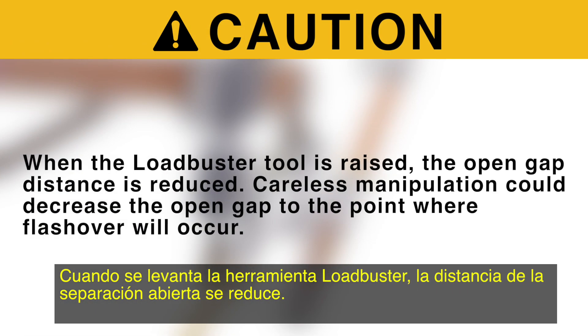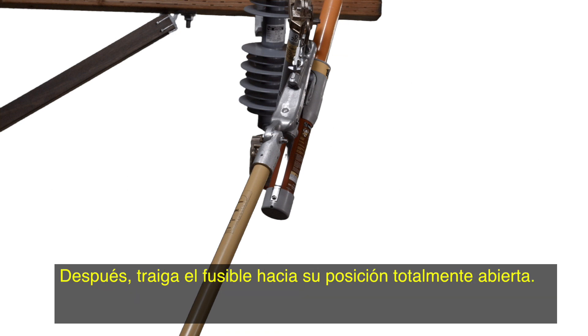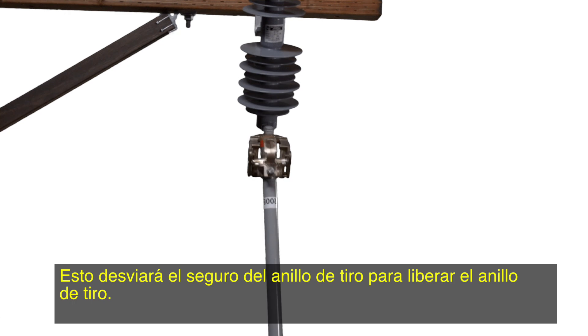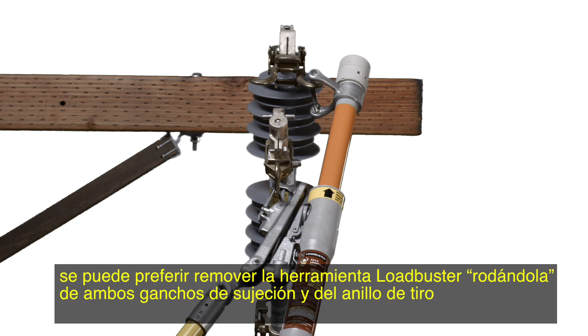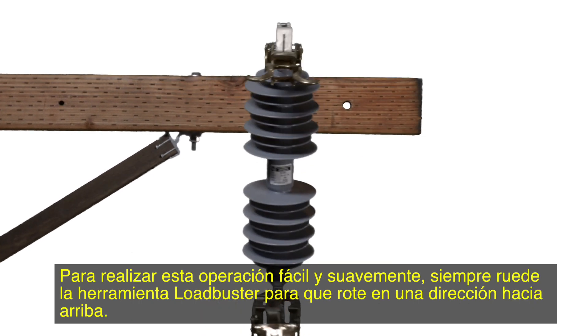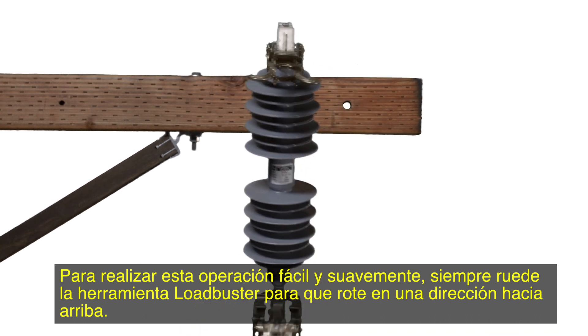Step 5. When the Loadbuster tool is raised, the open gap distance is reduced. Careless manipulation could decrease the open gap to the point where flashover will occur. Next, bring the fuse toward its fully open position. Remove the Loadbuster tool from the pull ring by turning the pole. This will deflect the pull ring latch to release the pull ring. On devices where the fuse will drop fully open by gravity, it may be preferred to remove the Loadbuster tool by rolling it off both the attachment hook and pull ring at the same time, merely by twisting the pole after the Loadbuster tool has been tripped and fully extended. To perform this operation easily and smoothly, always roll the Loadbuster tool so it rotates in an upward direction.